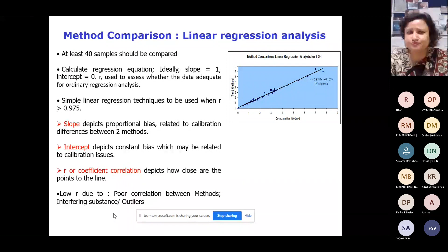So the slope depicts the proportional bias related to calibration differences between the two methods. The intercept depicts the constant bias, which may be related to calibration issues, and R, or coefficient of correlation, depicts how close the points are to the line. So low R is due to poor correlation between methods, interfering substances or outliers. If R is more than 0.975, then we accept that simple linear regression is verified.